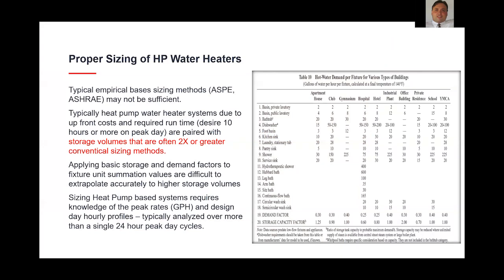So this is probably where one of the bigger challenges comes into play: how do we properly size these heat pump water heaters? Because as I mentioned, these are optimally designed to come on, operate almost at full capacity, and then shut off once you achieve that tank charge condition, once you've replenished those storage tanks. So really, they only start modulating near the tail end of that tank charge cycle. And because of economies of scale and the cost of this, what you're seeing is storage volumes that are 1.5, 2 times or larger than conventional domestic hot water heating sizing methods, with much more reduced generation rates from the heat pump water heaters.